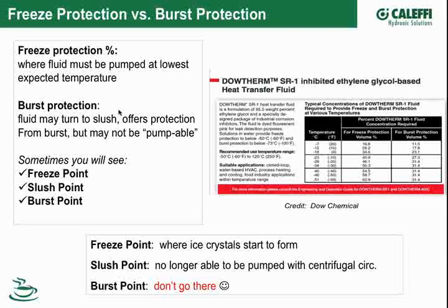Well, it doesn't really matter—the freeze point is irrespective of whether the fluid is moving or recirculating. The burst point, though, is a function of not just the fluid but also the equipment design. So if it's a stagnant fluid in a coil with a narrow gauge or tight spiral, thin gauge material, that's going to have a different rupture strength than heavy gauge, straight length steel pipe, say.